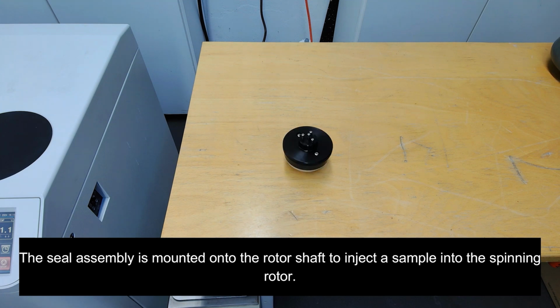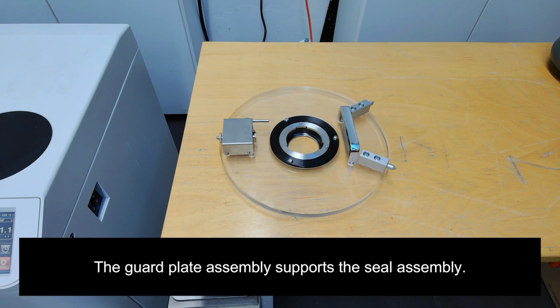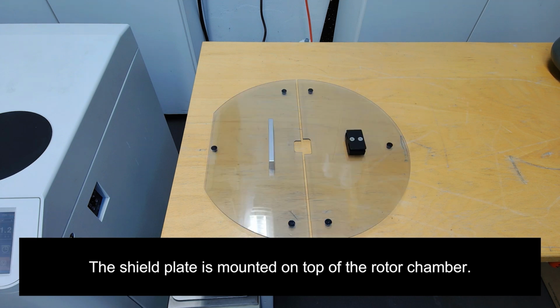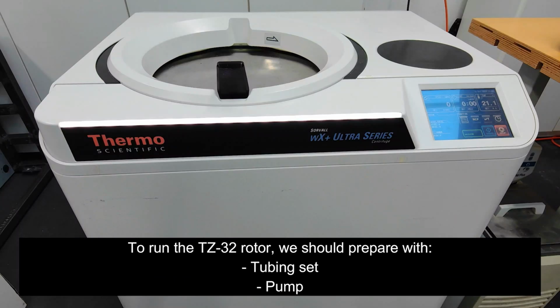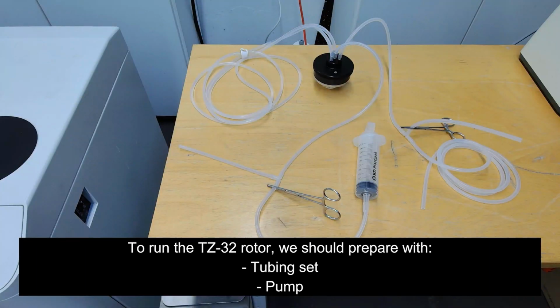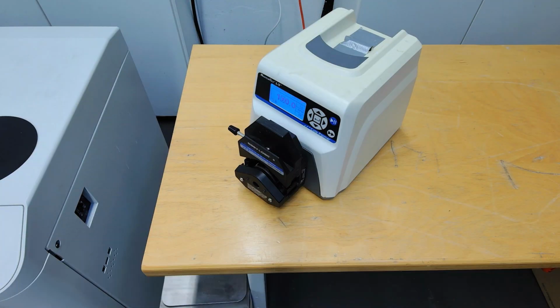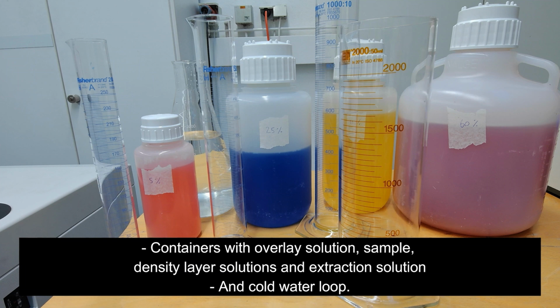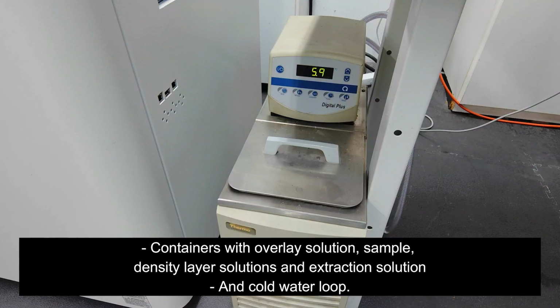The seal assembly is mounted onto the rotor shaft to inject a sample into the spinning rotor. The guard plate assembly supports the seal assembly. The shield plate is mounted on top of the rotor chamber. To run the TZ-32 rotor, we should prepare with tubing set, pump, containers with overlay solution, sample, density layer solutions, and extraction solution, and cold water loop.